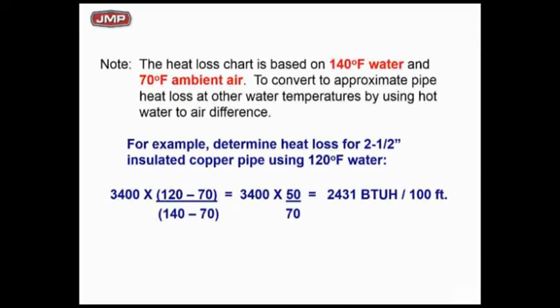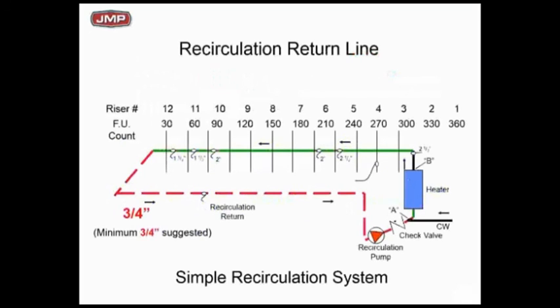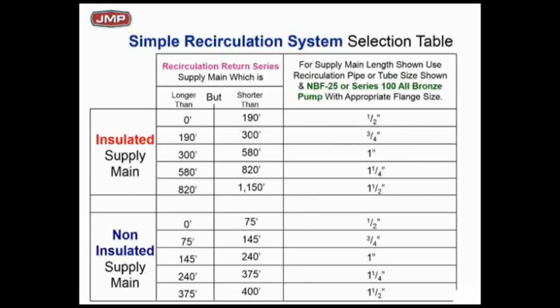This was based on 140°F supply water with an ambient temperature of 70°F. If you have a colder ambient or colder supply water, there's a correction formula. In this particular case, if we drop the supply to 120°F, the BTU heat loss is much, much less. So the chart we showed you is conservative at 140°F. Going back to our example: 300 feet of supply pipe, starting at 140°F at the water heater and ending at 130°F at fixture 12 — a 10-degree delta T — it takes 2 GPM to maintain that.